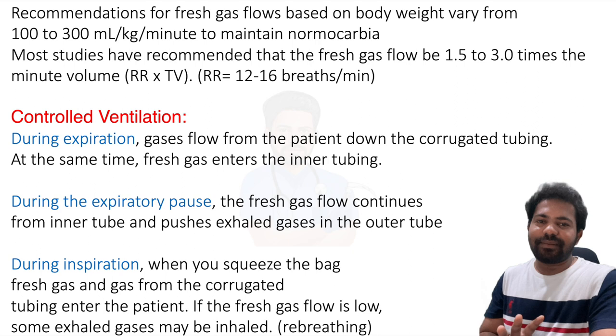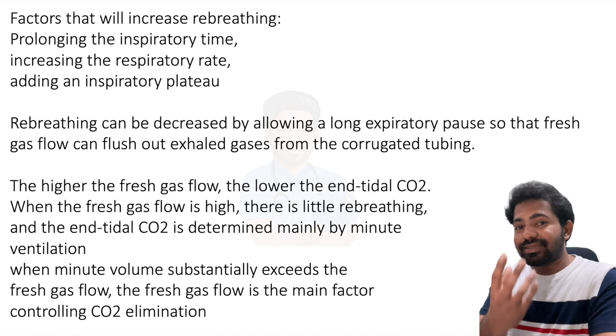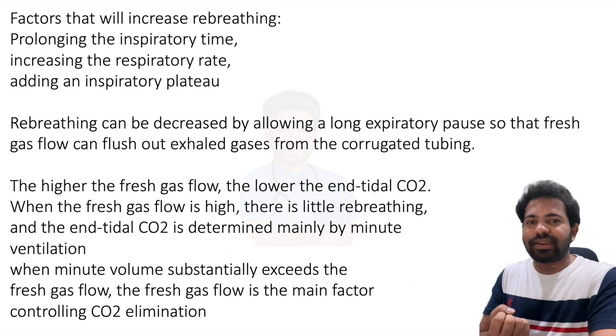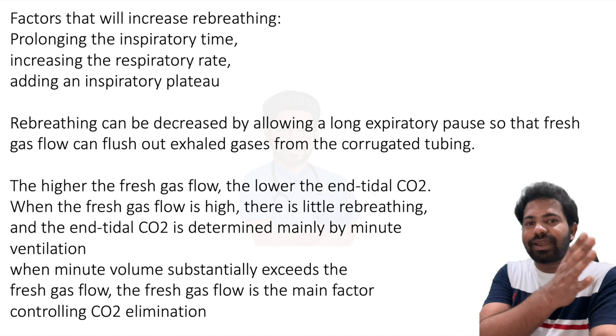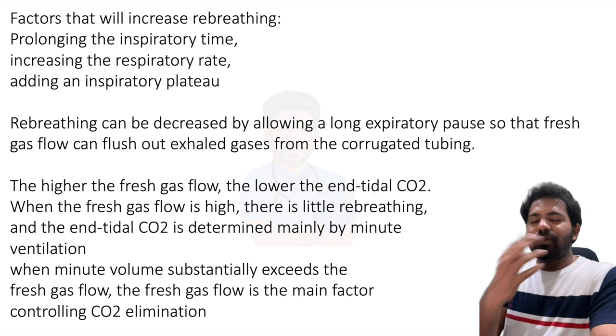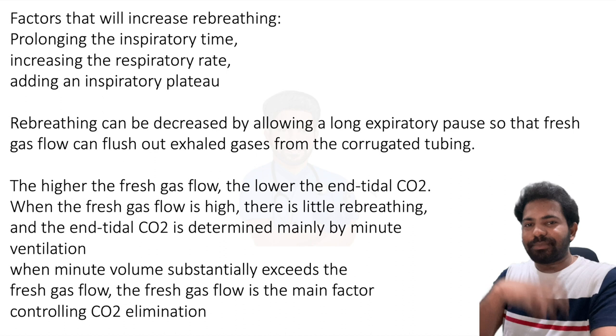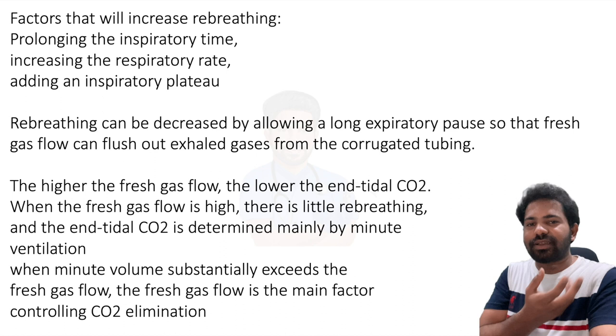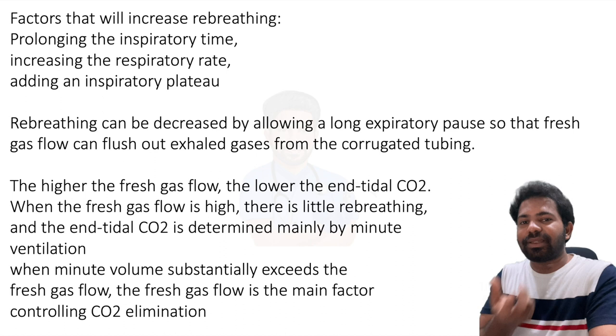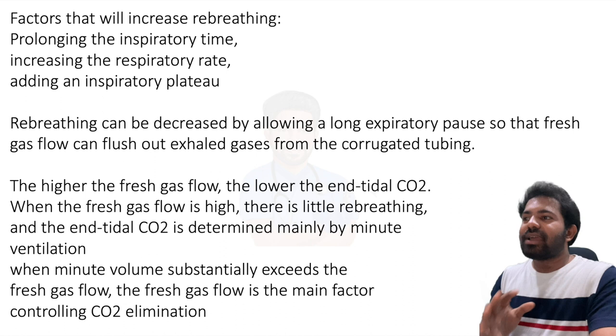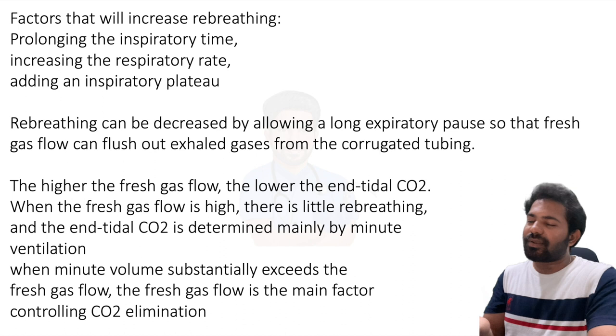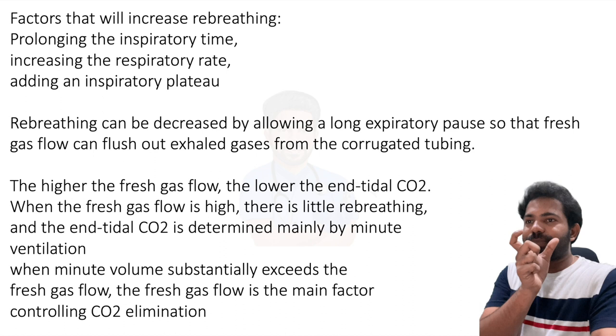Factors that increase re-breathing include: prolonged inspiratory time with less expiratory time, leaving less time for expired gases to vent out; increased respiratory rate, which limits expiratory time so carbon dioxide cannot be fully expelled; and an increased inspiratory plateau. Re-breathing can be decreased by allowing a long expiratory pause so the fresh gas flow can flush exhaled gases from the corrugated tubing.